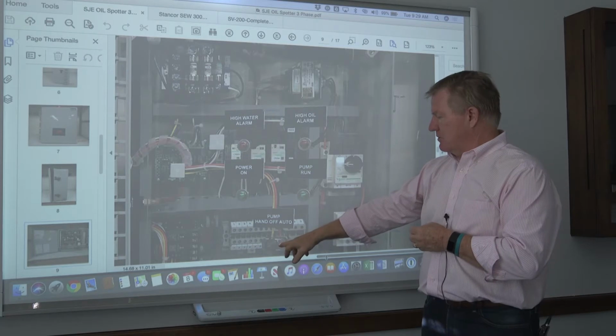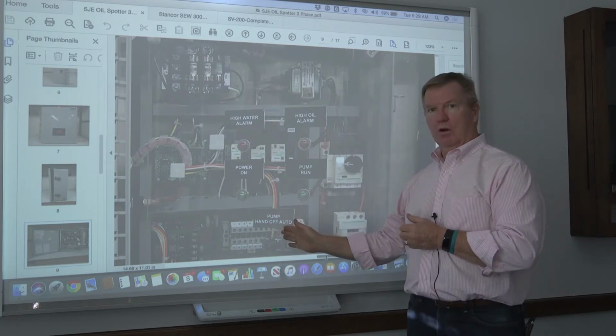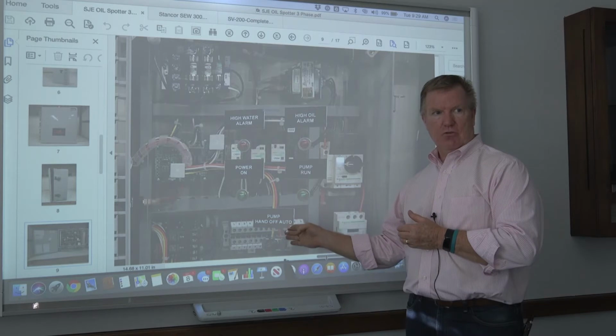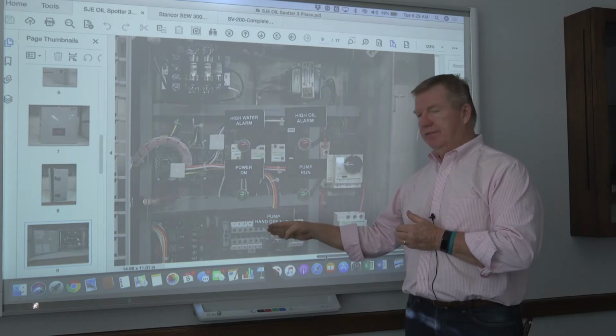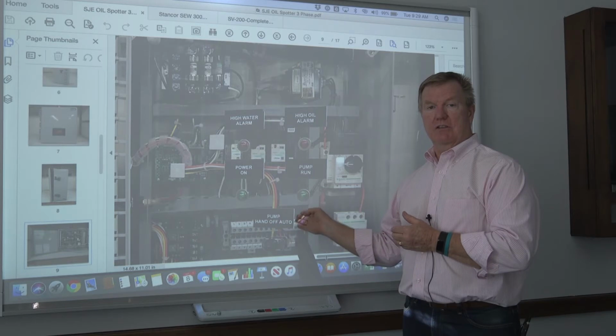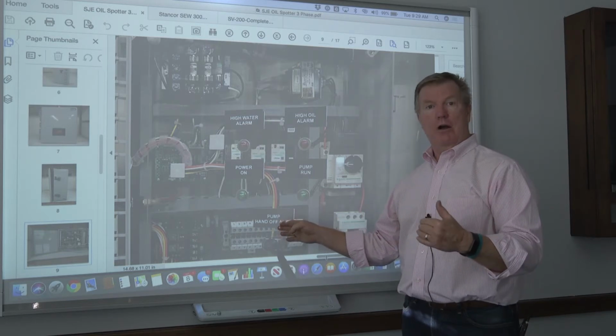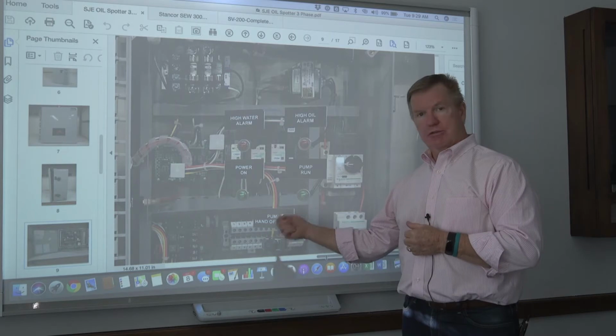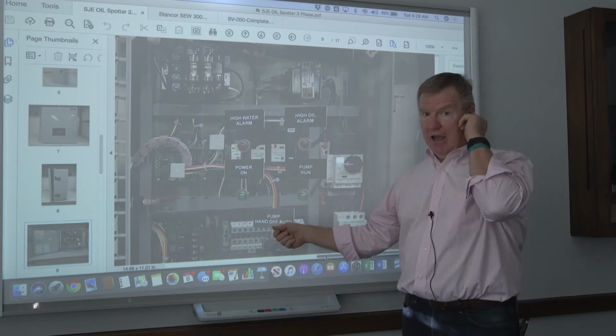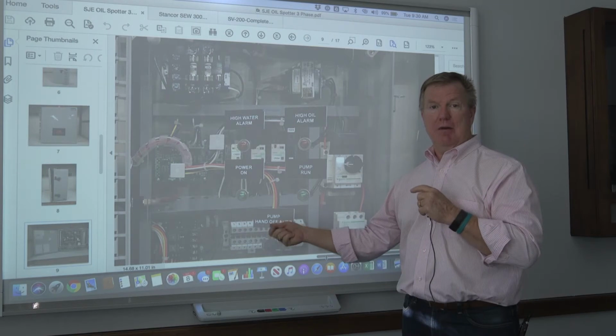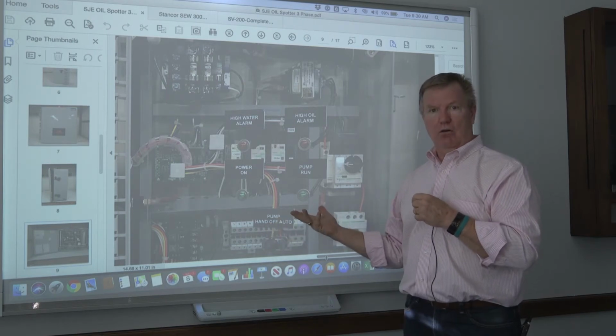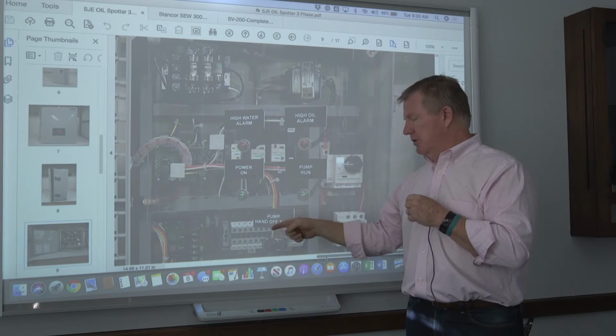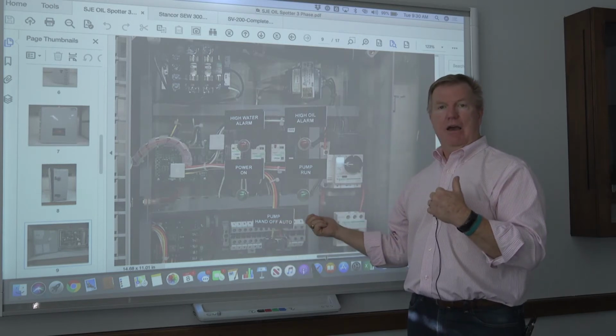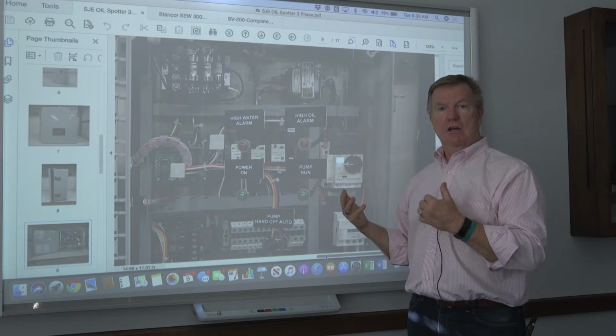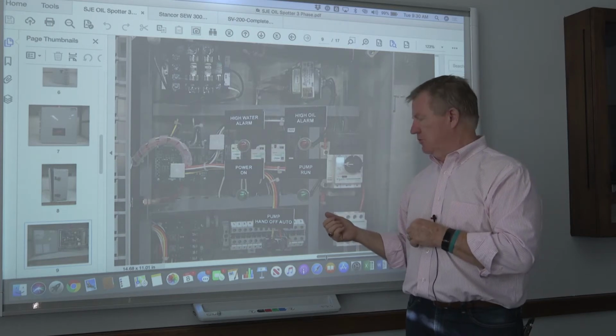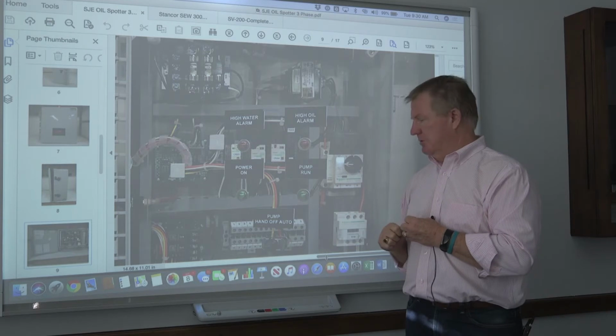Here's your pump HOA switch, which you can put in one of three positions. The center position is off, the left is the hand position, and the right is in auto. So if you want to turn a pump on and just run it by hand, you just flip this switch to the hand position. You have to turn it back off. It's not automatically going to turn off when you let go of the switch. So to run a pump, you put it in hand, and to have it operate according to the controls for the floats that are on the control panel, you would put it into the auto position.